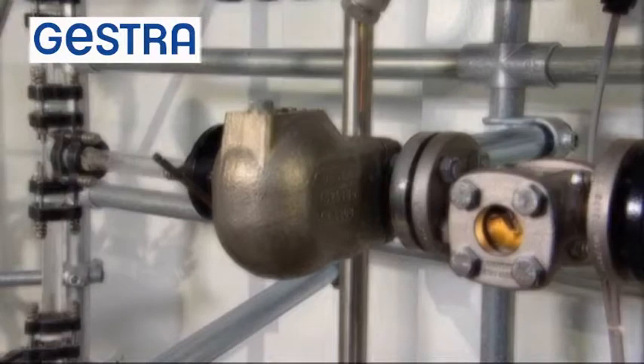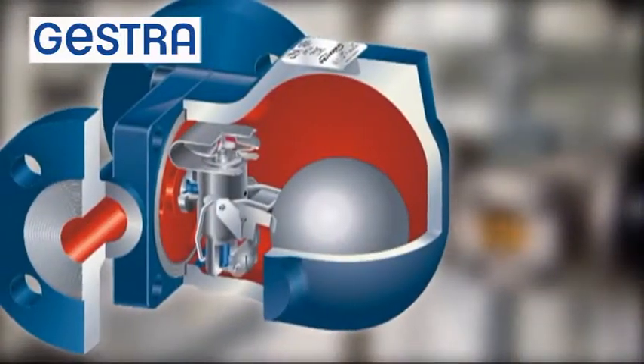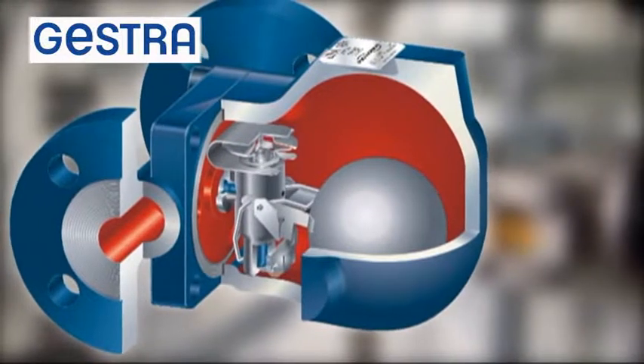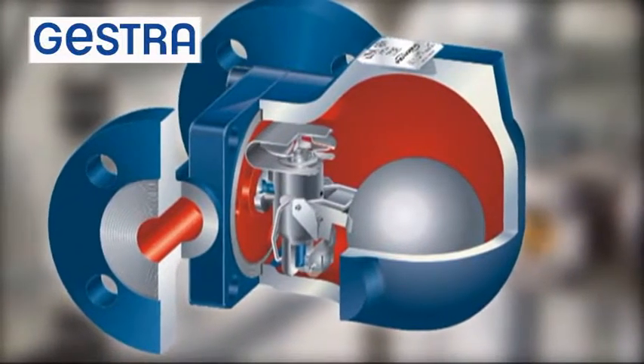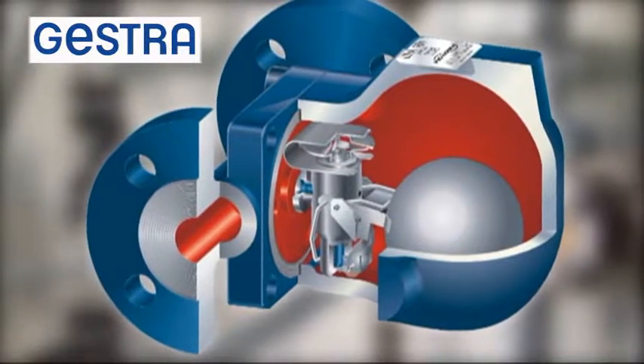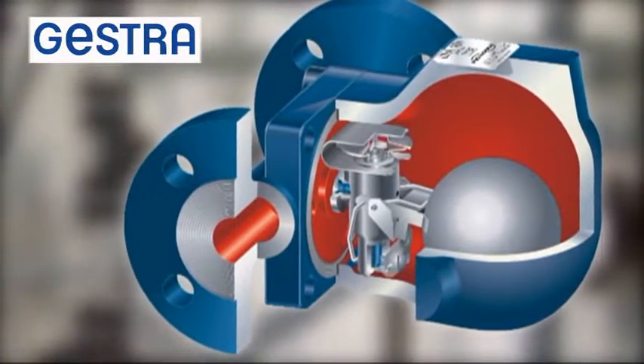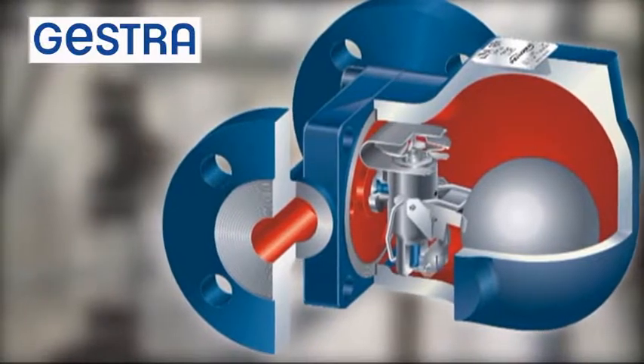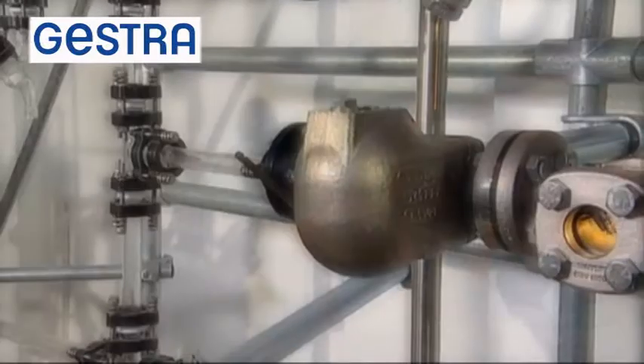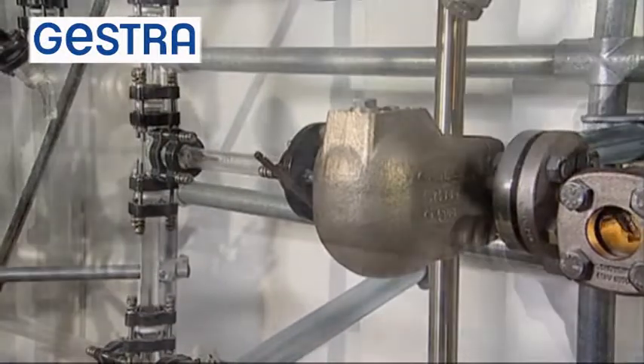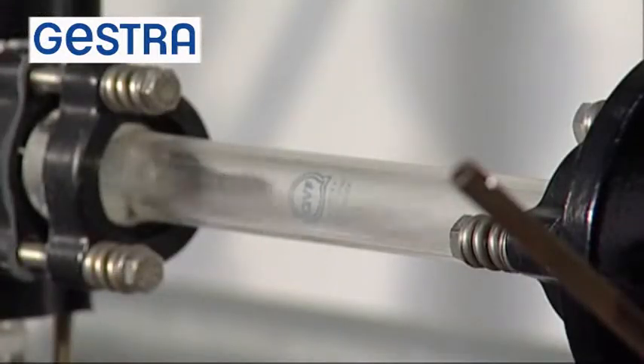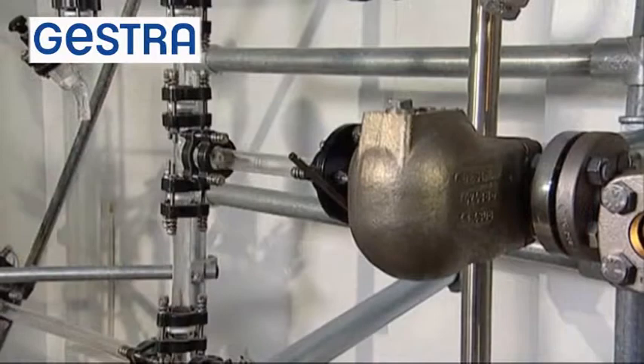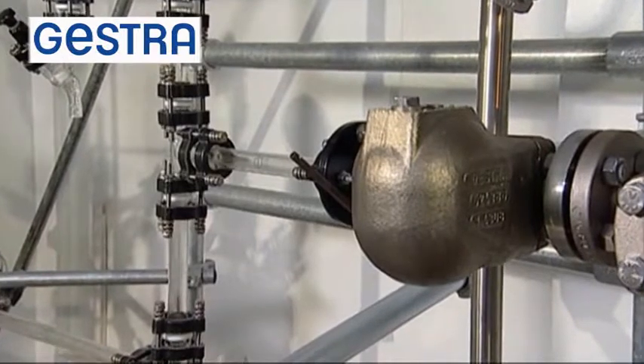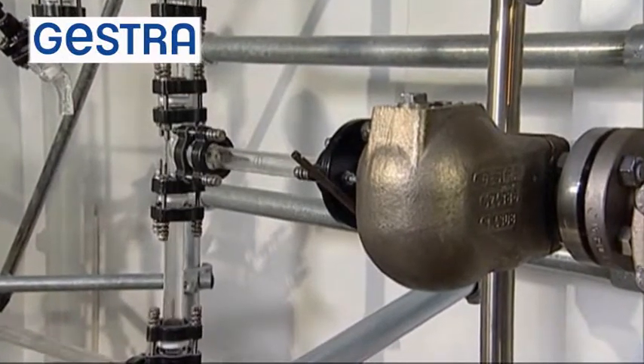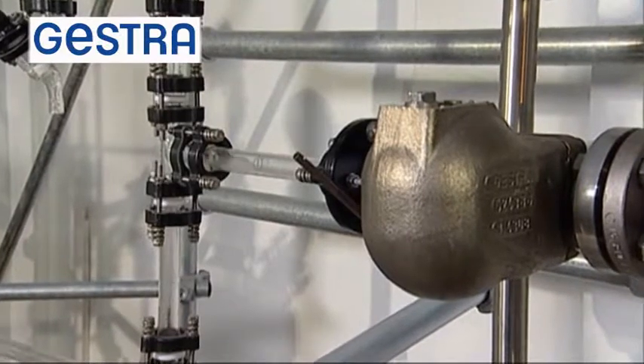Owing to the large volume offered by the body of a ball float trap, fluctuations in flow rate can be handled easily. The steam trap is not prone to hiccups. Because the flow velocities are low, particles of dirt can precipitate at the bottom of the body and will therefore not influence the seat tightness at the orifice. Ball float traps operate continuously. Because the float ball always floats on the condensate, moving up and down only slightly, the wear and tear is minimal, and the service lifetime of float traps is often 2 to 5 times as long as that of thermostatic steam traps.